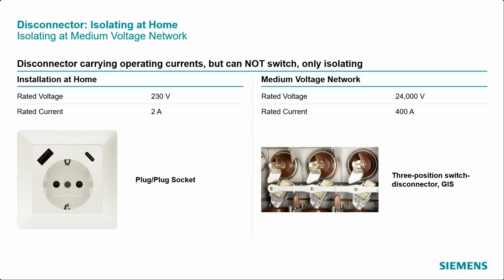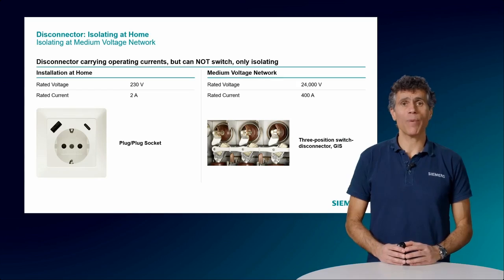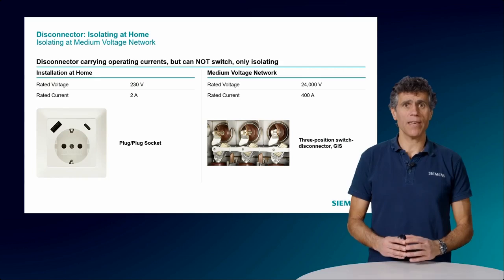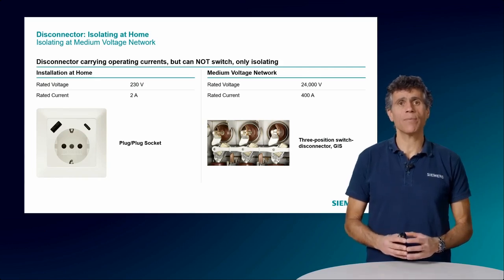And now to the disconnector. A disconnector, also known as isolator switch, is an electrical device designed to physically separate electrical circuits, ensuring no current flows through the section being serviced or inspected. It is primarily used for safety purposes, providing a visible gap in the circuit to protect operators during maintenance or when modifications to the electrical system are needed. A household plug can be considered a form of disconnector, as plugging in or unplugging a device physically connects or disconnects it from the electrical supply.